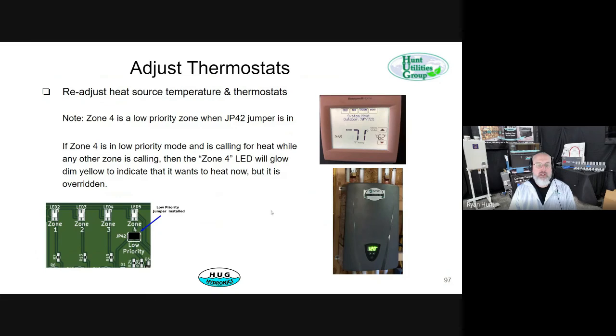Okay, now we turn on and adjust the thermostat. You'll see, watch the lights come on. Now, zone 4, there's a low priority jumper under it. And when that jumper is in place, if zone 1, 2, or 3 is calling for heat, zone 4 will not turn on. Instead, that light will turn yellow. Basically, you can think of that as a function for a garage, where you want to make sure the house, might be zones 1, 2, and 3, is fully happy before you put heat in the garage.